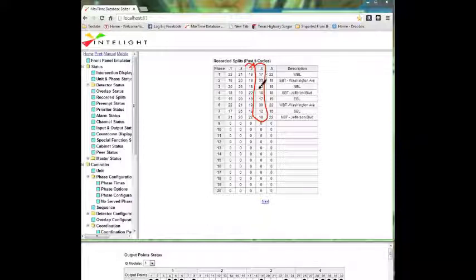we can see that phase 1 is 17, 2 is 30, so we extended to get the bus through in that case, and we subtracted on 3, 4, we extended 6, we subtracted on 7, 8. And of course you could go over to the next one and look at it, see what types of minor adjustments it made. But it's only a couple seconds here, a couple seconds here.